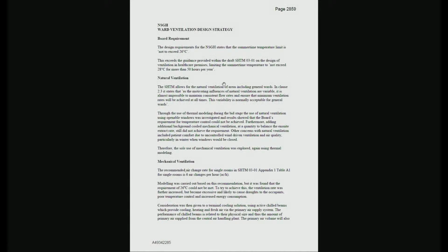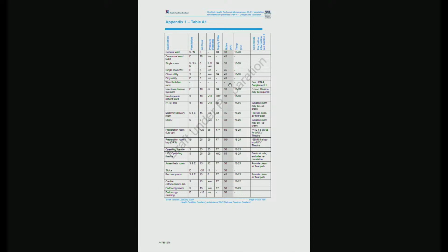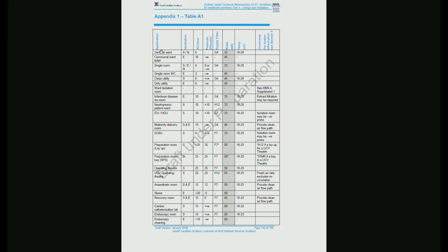That's bundle 16, page 483. The top row is the general ward we're referring to. How many air changes are required for general wards now? 6. And the filter type? G4, much lower grade than a HEPA filter. And no requirement on any particular pressure gradient? No. The temperature range is 18 to 28.